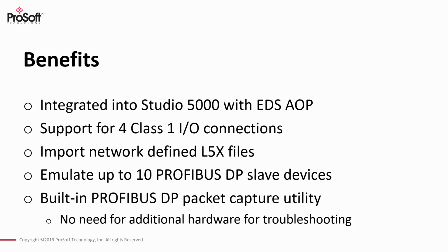And so with the integration into Studio 5000, we utilize the EDS AOP, that's the electronic data sheet add-on profile. And that allows us to do up to 4 Class 1 I/O connections, each one of them with up to as fast as a 10 millisecond RPI time for all 4 connections.